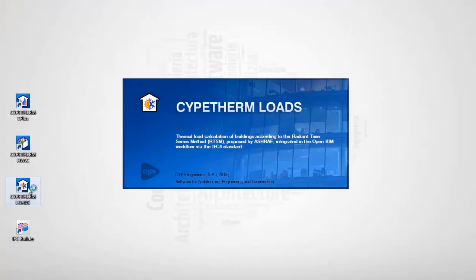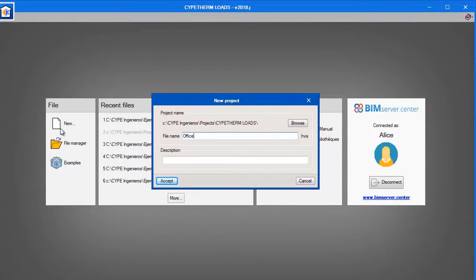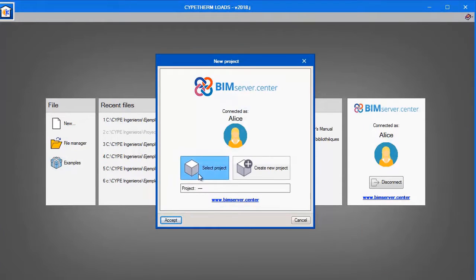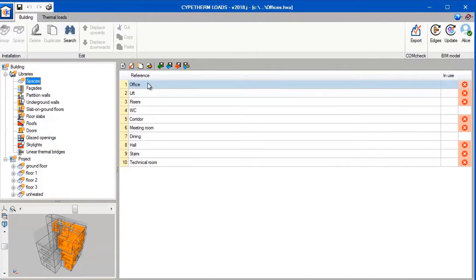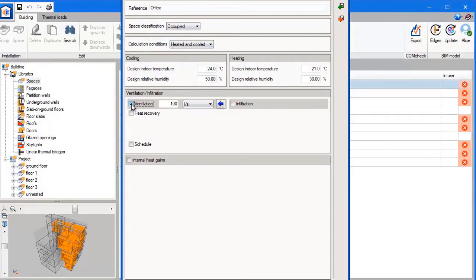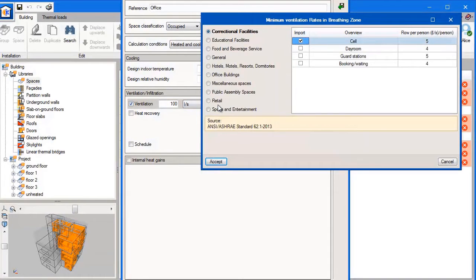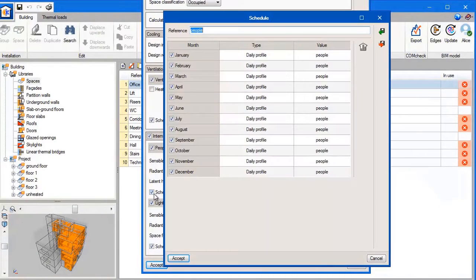We are now going to open up CYPETHERM LOADS. CYPETHERM LOADS is used to analyse the heating and cooling loads in the building. We create a new file and we want to select the offices that we just created, and we import the office block. We need to open each of the spaces and select the design conditions we wish to use. We need to select the correct value for ventilation, so we open the ventilation library and look for office space. Once we find office space we can select that and import that figure. It's important to define schedules for each of these options.